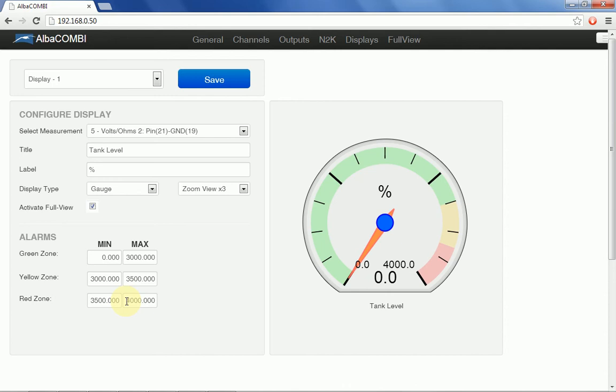Now say that in this case there is not much sense to talk about alarms because this is just a tank level. I would say that the green zone is 0 to 100%. Yellow zone, because I don't want to have any yellow and red zones, so this is a little trick which I do. Yellow is 100 to 100, and red is 100 to 100. So in this way, I've done a 0 to 100% tank indication, all green with the percentage indication. If I press save, it's saved.